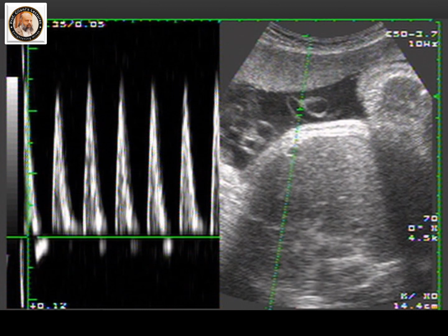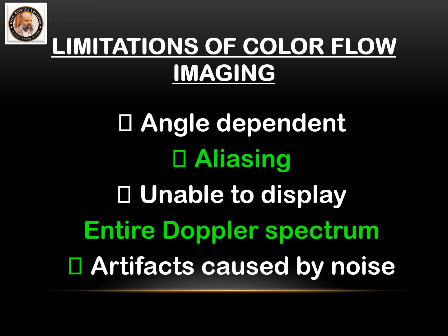The power Doppler is not angle dependent. There are limitations of color flow imaging, like it is angle dependent, there will be aliasing, it is unable to display the entire Doppler spectrum, and artifacts caused by noise. That's why we go to power Doppler. Power Doppler is less angle dependent, with no aliasing, less noise, a homogeneous background color, and increased sensitivity to flow detection. With this, we finish these 105 slides for basics of color Doppler, the ABC of color Doppler.